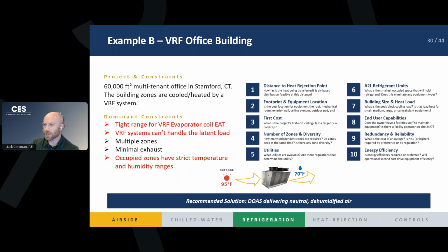The only time I will say you can use an ERV is if your mixed air ends up being a very, very low percent of outside air. So if you only need like 25 CFM of outside air, but you need like 1,000 CFM of return air, that very, very small latent load is potentially handled by your VRF system. So you just got to check the manuals. All VRF systems can handle some latent load, but on any of your hottest days of the year, right, you're going to need a DOAS system to handle that.